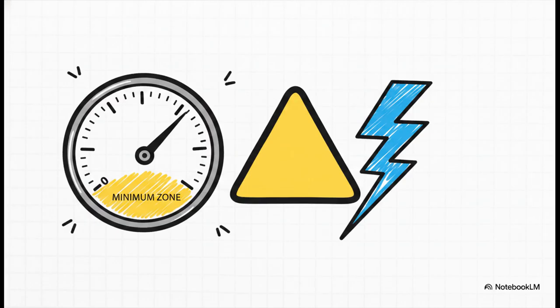It is incredibly important that you do not treat this as just another optional maintenance metric. Insufficient SF6 gas directly compromises the breaker's physical ability to safely quench an electrical arc during an interruption. If that gas is low, you don't just have a maintenance issue. You have a massive, safety-critical hazard on your hands.